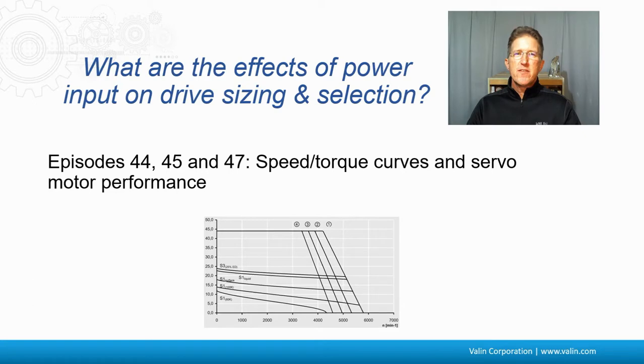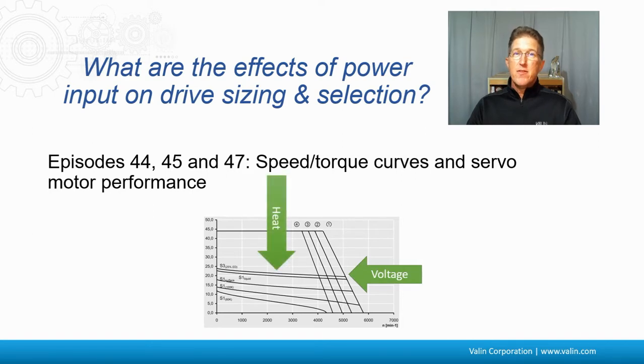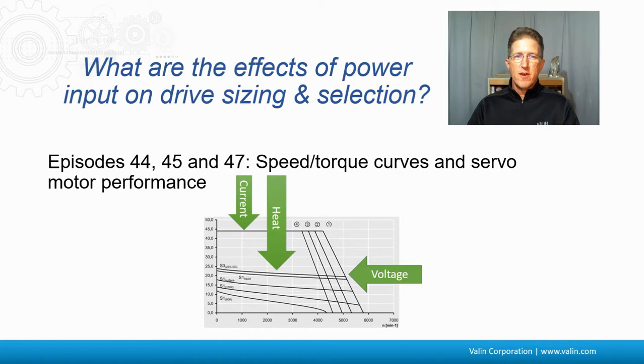What are the effects of power input on drive sizing and selection? In episodes 44, 45, and 47, we talk about speed-torque curves and servo motor performance. The quick summary is: voltage affects the speed capability of the motor; thermal capability — the heat dissipation — really affects the continuous capability of the motor; and the current capability from the drive, what it can supply, affects the peak torque of the motor.